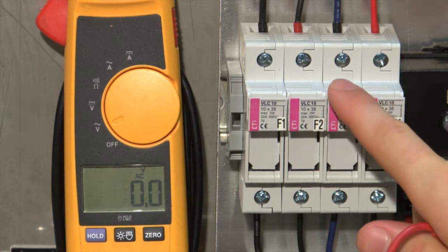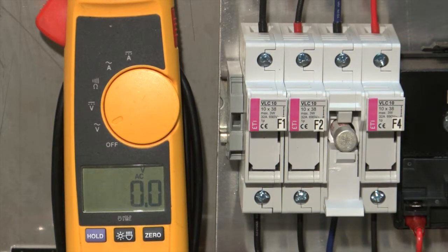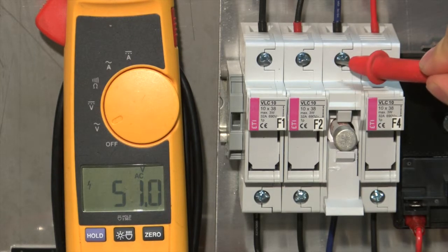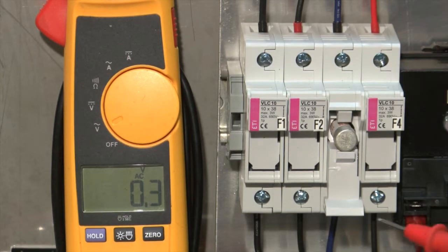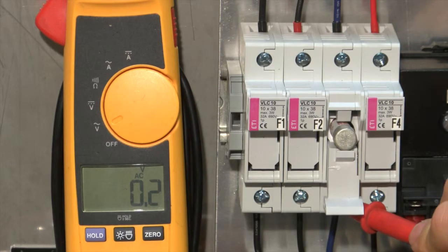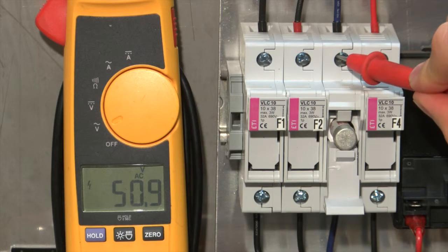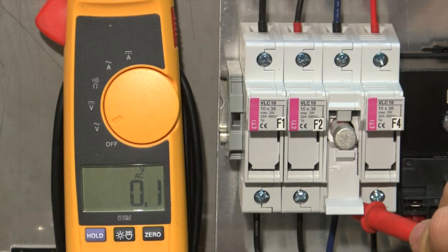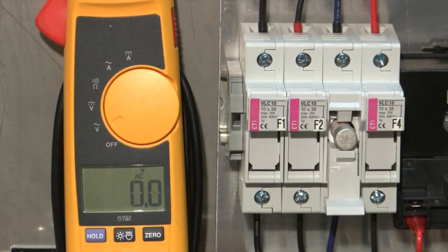In the scenario of a blown fuse, we would see the 48 volts coming in but no voltage coming out. This would tell you that that fuse is blown. Check the wiring diagram attached to your unit for all fuse ratings. These fuse ratings must be followed for your system to work correctly and be protected safely.